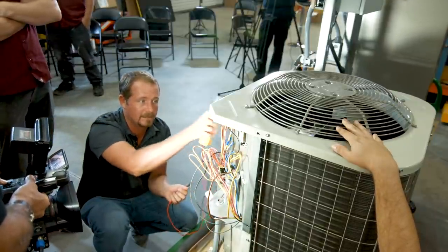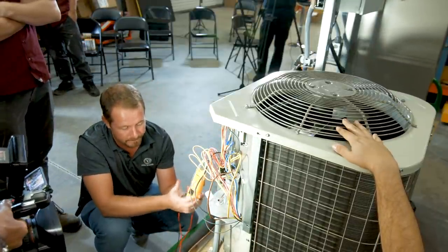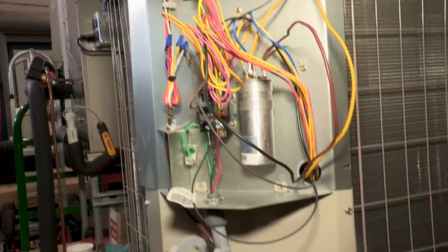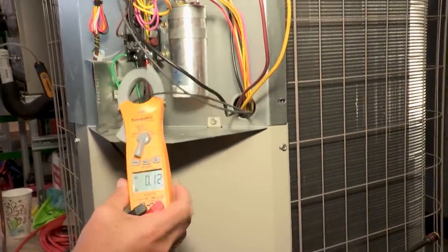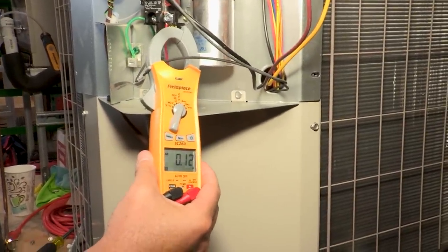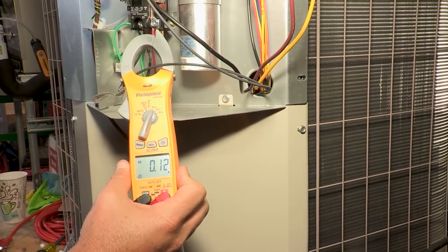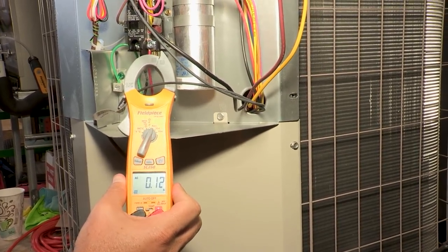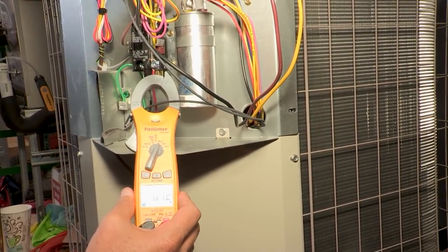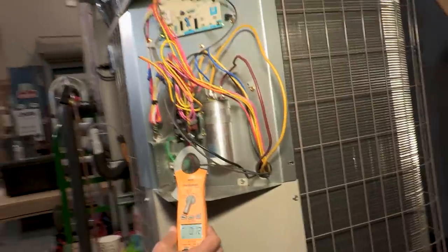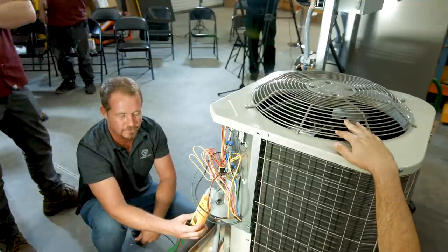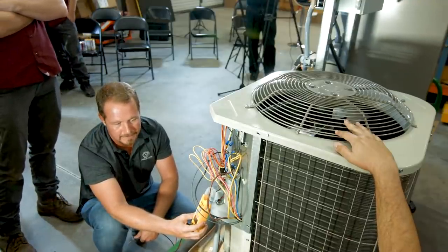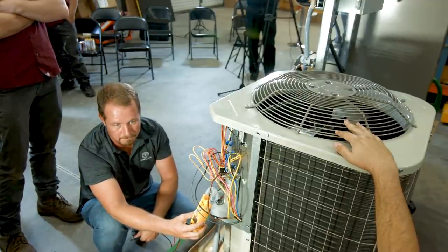And if we take our amp clamp, this would be our final test to see if our crankcase heater is working. Very low, 0.12 amps, but that's all that you expect in this case. It's not a really hot heater. It's just enough because it's sitting there all the time. The whole time it's off, it's drawing a little bit of current, and that's keeping that compressor crankcase warm.